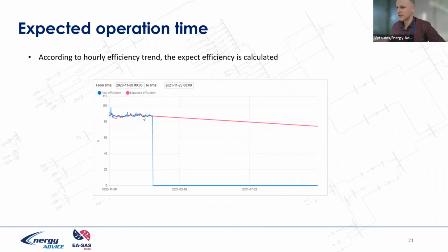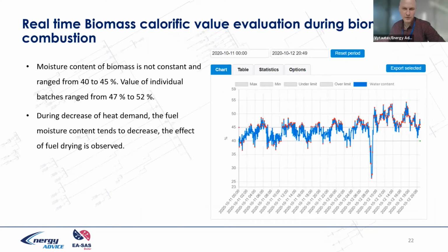Of course, we estimate efficiency, and we can extrapolate how it would decrease and what would happen later. And water content mostly affects all modes inside the boiler. You can see the dynamics here. When we reach 40 to 45, it's just indicators, but you can see how it dynamically changes over time. It is day 11 and 12, so it's two days, nearly 48 hours. And you can see some dynamics when the boiler was stopping, reducing heat, and the fuel inside was drying, so it dries and burns later. But the mode inside the boiler is like the fuel is dried.